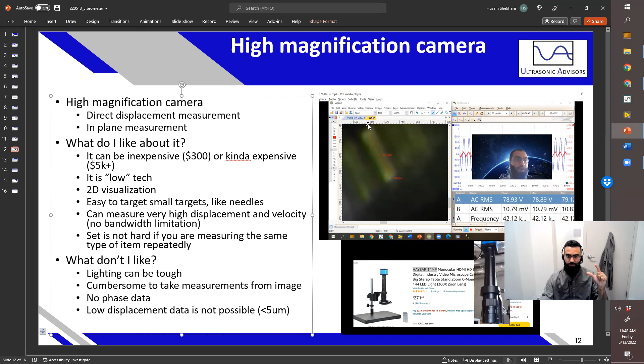So going back to this high magnification camera, basically the way it works is you shine light on a certain portion of your transducer, and it reflects a little spot of light back onto the camera. When there's oscillation, it creates a blur, so that one spot becomes larger, and it becomes a blur like this over here. And you can actually measure. Let's go over here.